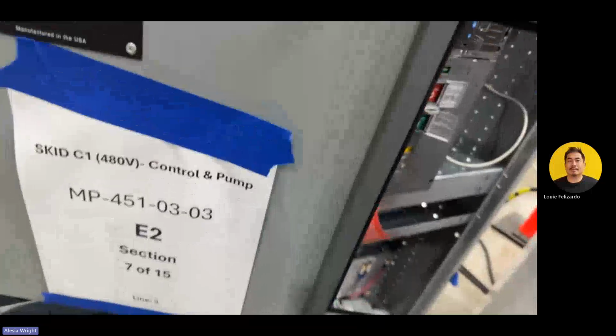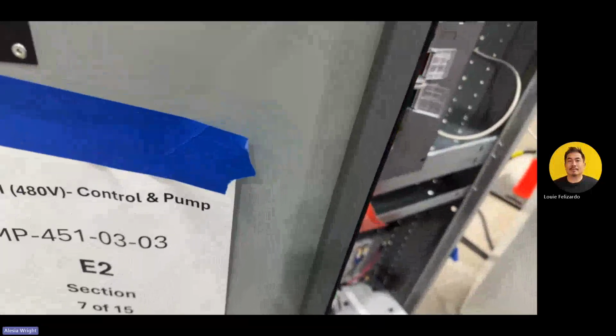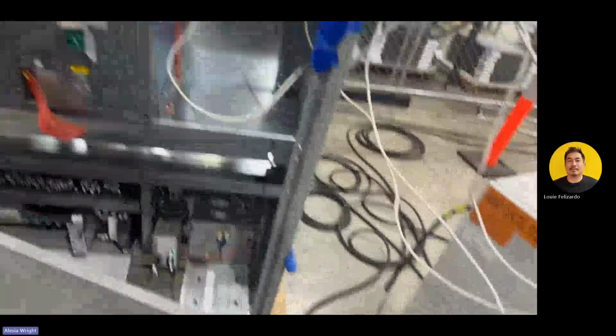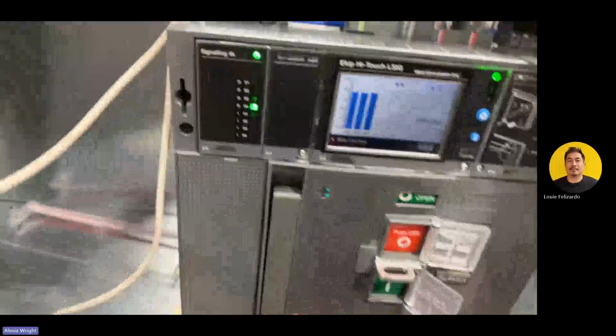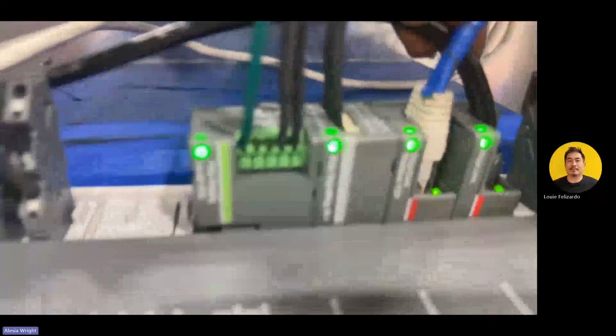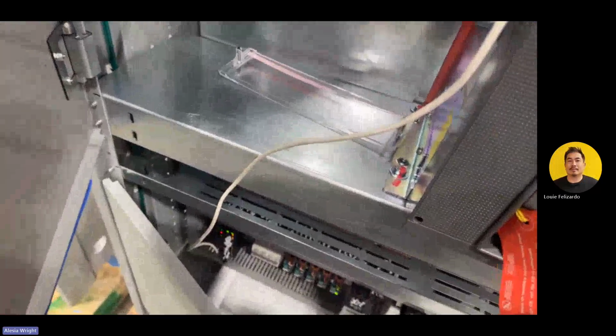If you don't have that, you're gonna get an error message on your touch screen that says communication error, something like that. And it'll tell you the source. It'll say source one, source two, communication error. So go back and make sure they're in there. Just push them down. Make sure you see green and amber clicking on everything. And even on your touch screen, it's got a green and amber light. Anyway, green and amber light on everything. Make sure you got those good, and then you should be good.